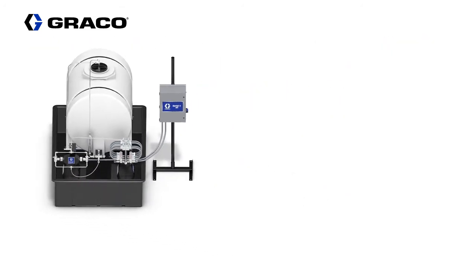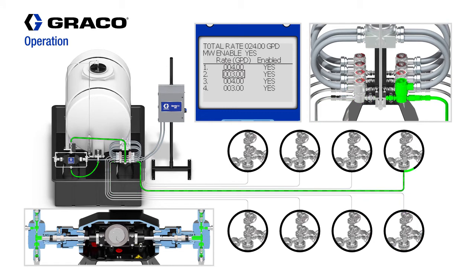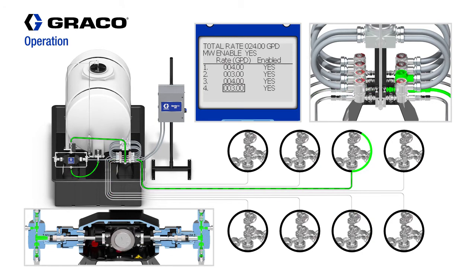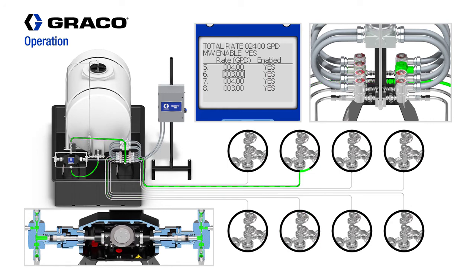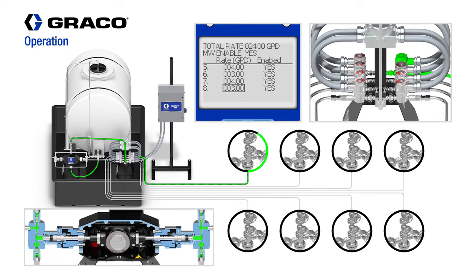This demonstration shows an 8-point injection configuration. Using the Harrier Plus MPI, you can enable or disable individual solenoid valves directly on the controller or remotely using the Harrier Plus web portal. From the same screen, you can set the desired flow rates for each injection line. If a line is enabled, Harrier Plus MPI will send a signal to the corresponding solenoid valve and will dispense the desired amount of chemical in that line.